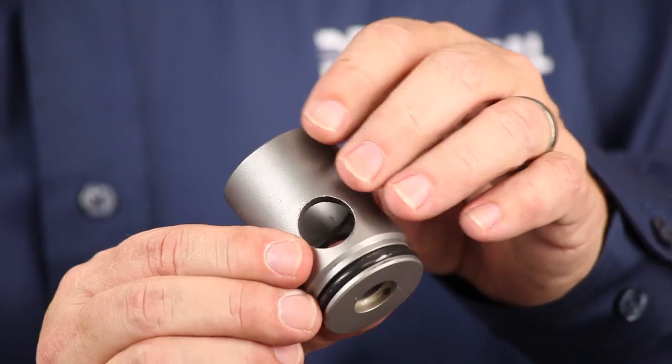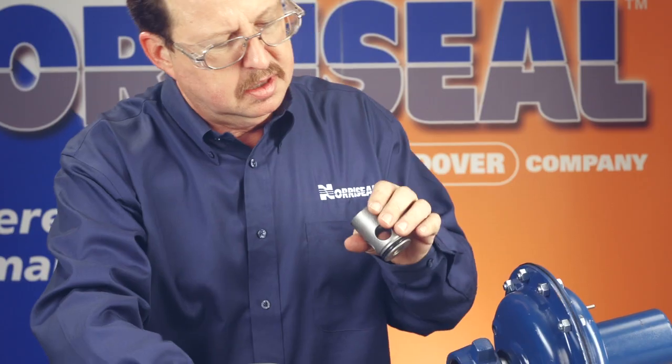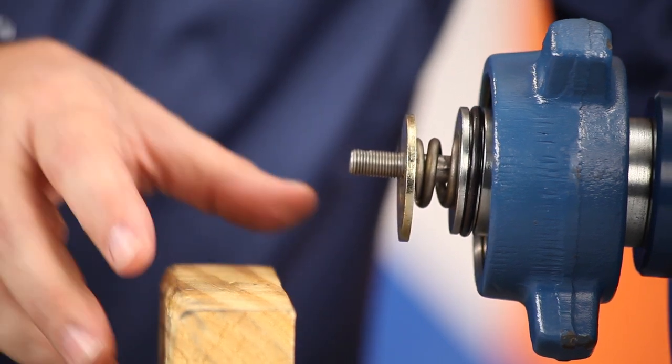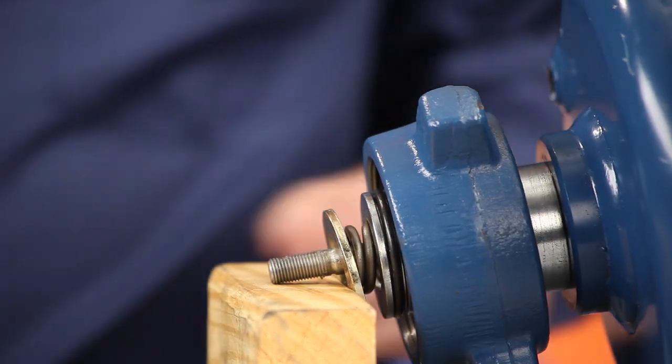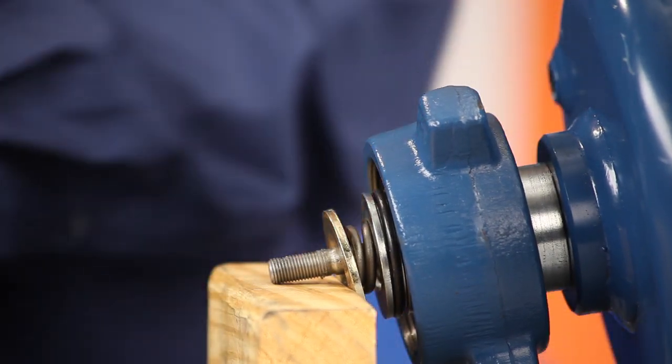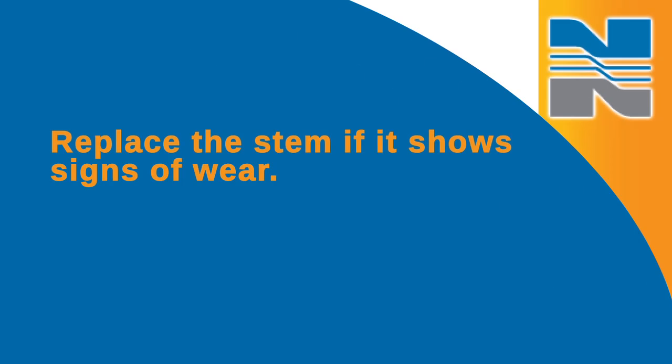Examine the valve plug and seat to make sure there's no damage to the sealing surfaces. You also want to examine the stem for pitting, scratches, or damage in the area adjacent to the packing and o-ring. Replace the stem if it shows signs of wear.